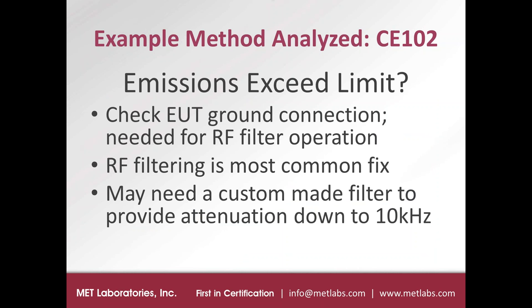And the question is, what if you are finished doing the test and then you see that your emissions exceed the limit? What can you do about that? One thing that's quick that you can check is to make sure that your EUT is properly grounded. A lot of RF filtering relies on the filter having a proper platform ground connection in order to have a path for the unwanted RF currents to flow to.